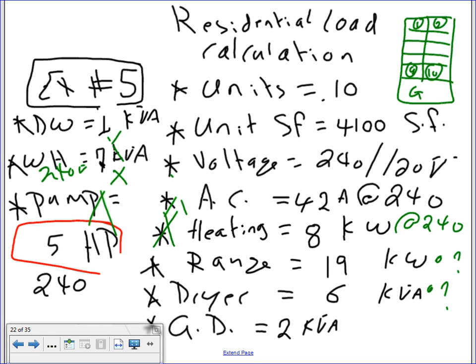So just a reminder, my AC is dropped, my heat will be dropped, pump will be dropped, and also the water heater. Anything 240 will be dropped, except the dryer and the range, because they are 240/120, there's a 120 with them. We count only 70% of them, okay? And that's what we're going to go with.